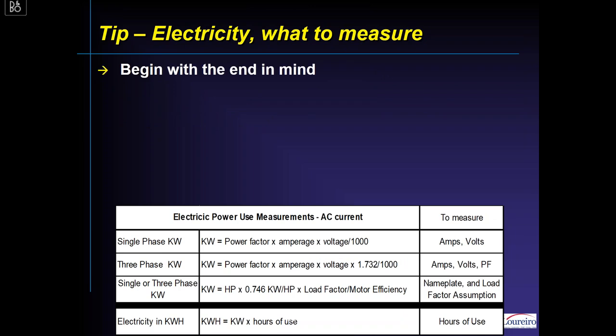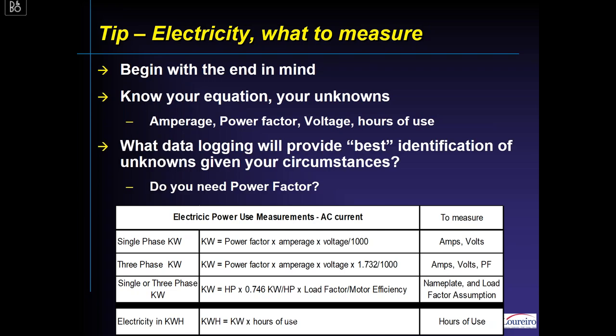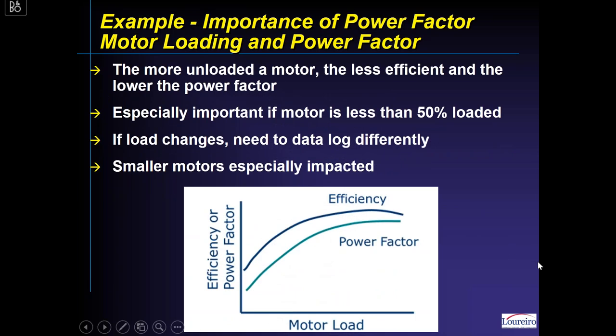Begin with the end in mind: know your equations and your unknowns. Are you just needing amperage, or do you also need power factor? Should you get voltage — continuously or just a multimeter reading upfront? Do you want hours of use to generate energy calculations? You have to do your data logging to best identify your unknowns. Do you need power factor? For many data logging situations you don't, because there are no real motor loading changes — but you have to think about that.